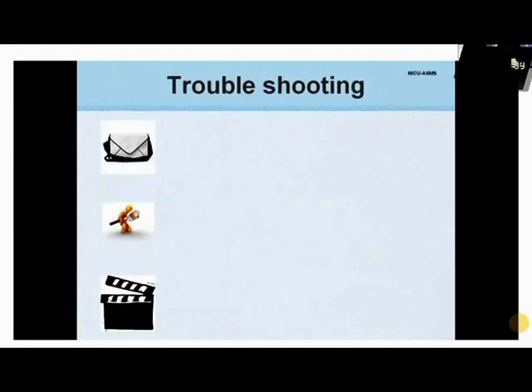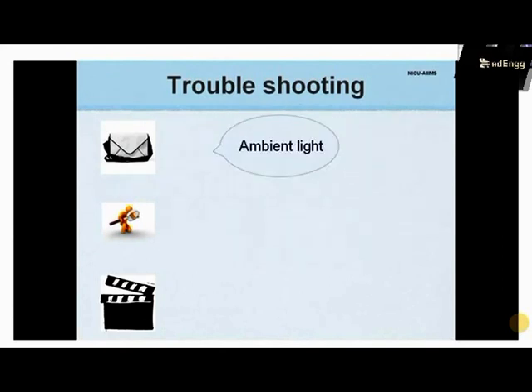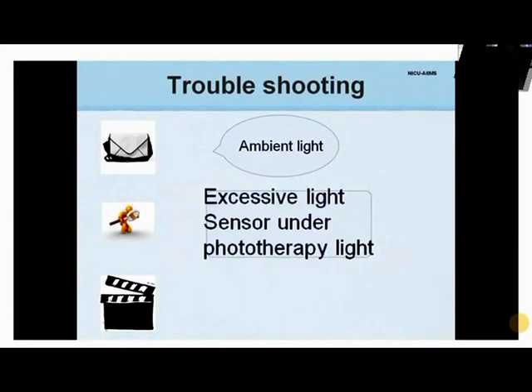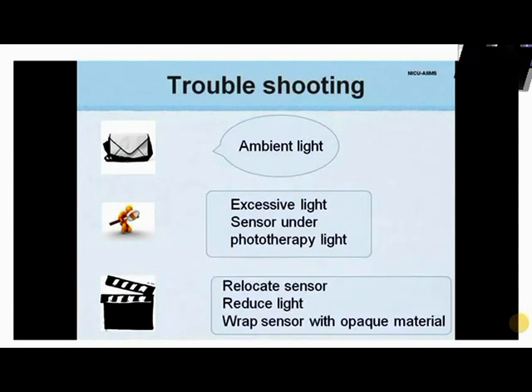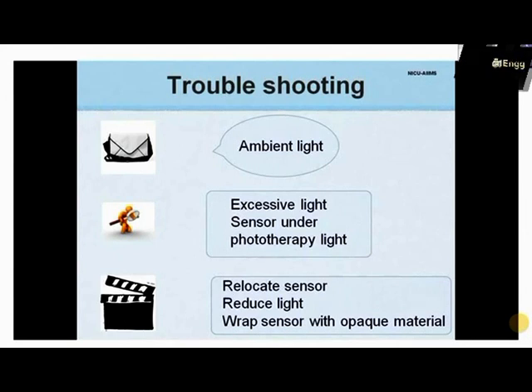Problems are anticipated with any equipment and should be fixed by analyzing the cause and finding a solution. If there is an ambient light message, it means excess light is shining on the sensor — relocate the sensor to a more shielded site or reduce the amount of light. If the baby is under phototherapy, the sensor must be wrapped with an opaque cloth or carbon paper.